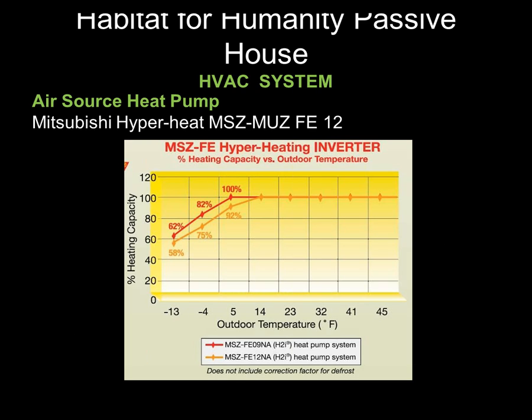The nice thing about these new air source heat pumps is they can operate at very low temperatures. This one can go down to minus 13 degrees Fahrenheit, and it performed very well this past winter, even when the temperatures plummeted below zero. It was more than enough to meet the heat demands for this building. In fact, it's only providing it at one specific point in the building. It's not a ducted system. It's a point source heater in the living room. And that point source, given the strength of the envelope, allowed every room to be within a couple degrees of each other, even on the coldest days in the winter.